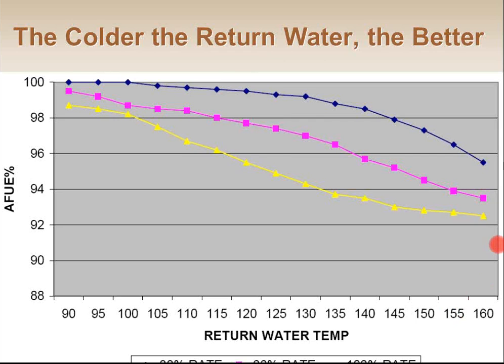I'm going to keep the heat exchanger the same size because I can't swap out heat exchangers every 5 minutes. I'm going to reduce the firing rate. So it's kind of like having a triple oversized surface area. So I can get more surface area by turning the burner down with a modulating or staged burner, and I can get more efficiency by turning the burner down or by lowering the water temperature, or both. So the question becomes, how cold is too cold of water to send to the condensing boiler?